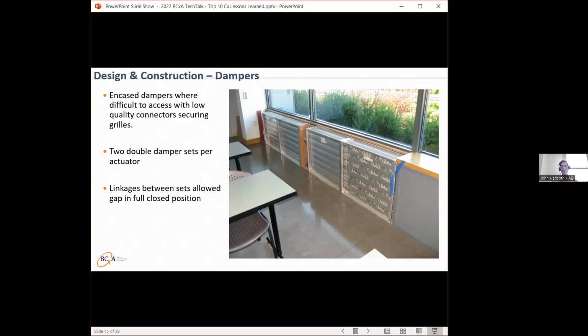So this was a quick identification of the problem for why unintended intrusion was happening, even though you had double sets of dampers stacked in front of each other and behind each other. So that was an obvious issue that had to be rectified to just stop infiltration. And if you look closely, you don't even see gaskets on these dampers. So there was a problem there with the quality of the damper sets, on top of the double sets next to each other using one actuator.